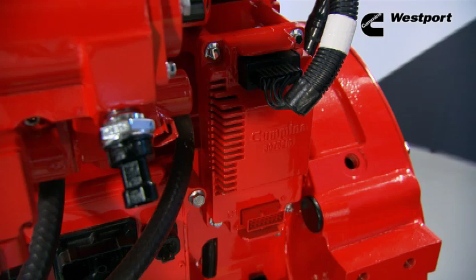A key maintenance factor for both natural gas and diesel engines is the oil drain interval, which is duty cycle dependent, so consult the owner's manual for details. Cummins Westport natural gas engines require special natural gas engine oil available from most major oil suppliers. The engine oil specification CES 20074 is important because natural gas engine oil has different properties than diesel engine oil. A sulfated ash limit of 0.6% has been placed on all engine lubricating oil recommended for use in Cummins Westport engines. Natural gas engines also require less detergent in the oil as there is no soot residue.